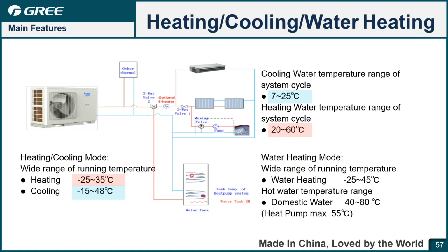And for the hot water, the operation range is -25 to 45 degrees Celsius. For the domestic hot water, 40 to 80 degrees Celsius. However, the hot water you can get from the heat pump is a maximum of 55 degrees Celsius, which means the range from 55 to 80 is achieved by the e-heater. Yeah, it's achieved by the e-heater. Okay.